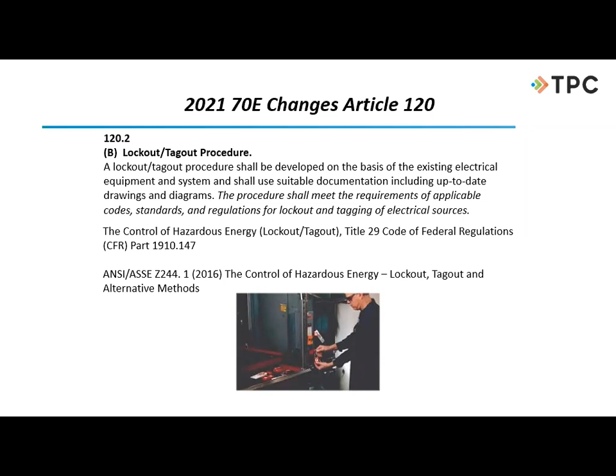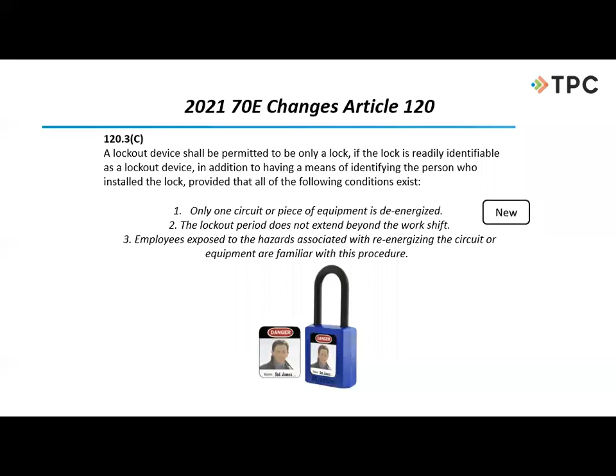This is talking about if I only want to use a lock and no tag, if I don't want to put a tag on it, which, of course, is our choice. But if I do want to use only a lock, I do have to satisfy 3 conditions now. And it has to be just one piece of equipment that I'm locking and tagging out. It has to be within the shift that I'm working in. And any employee exposed to those hazards associated with re-energizing it are familiar with our lockout tagout procedure. So they're just re-emphasizing the fact that I can use just a lock if I can satisfy 3 conditions.